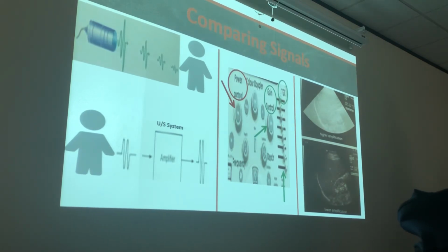So when y'all go to clinic, just adjust those things, just mess with it so you can see what it is. But when you put it on abdomen, on your preset, the acoustic power and stuff is already adjusted, okay? The preset number changes according to the different anatomy you're using and the different transducer you're using, okay? So the output power won't be the same from transducer to transducer, okay?